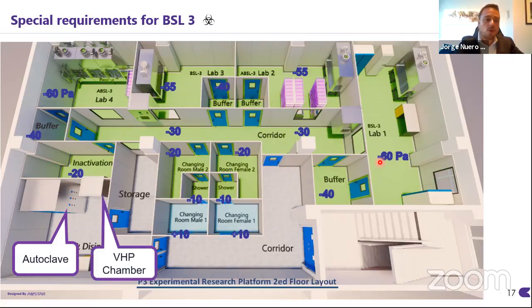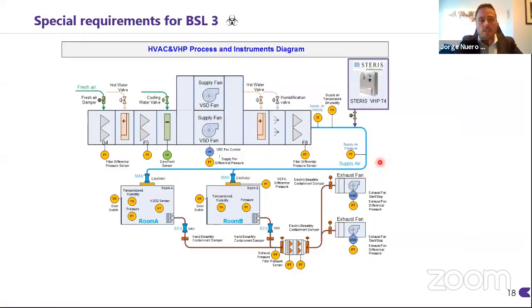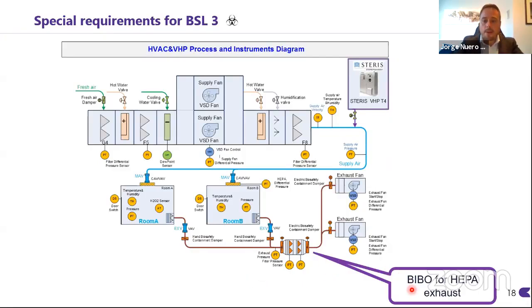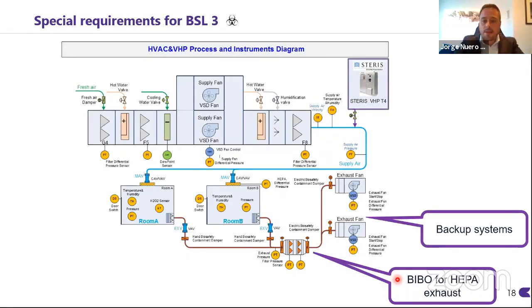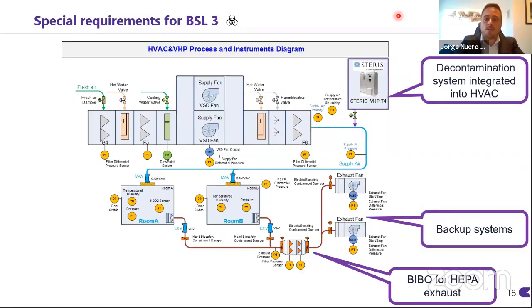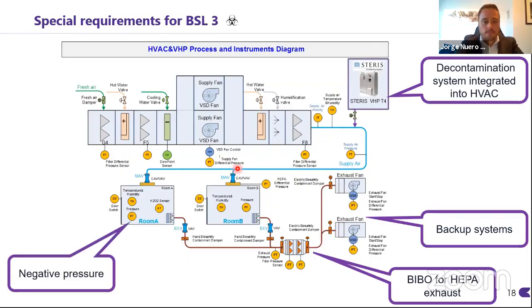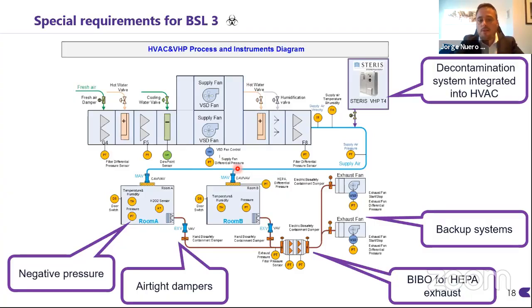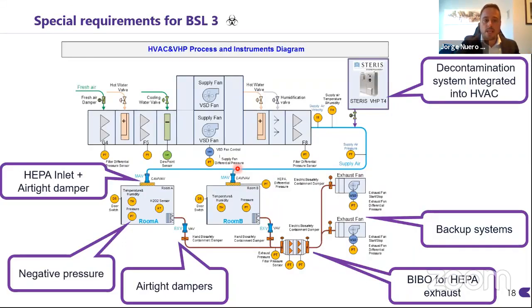We have also some other devices like an autoclave and a VHP chamber. So this is the general schema for a biosafety level 3 laboratory, different from others in that we usually have a bag-in, bag-out for a HEPA housing. This is to allow changing the filter without putting our operator at risk. We have backup fans, so in case this fan fails, we have another fan just in case. We have a decontamination system integrated into the system, and we have, as I mentioned before, negative pressure and airtight dampers. These are special dampers for biosafety level 3 laboratories, where we can guarantee that when the damper is closed, there is no air going out from the rooms. The same for the inlet.